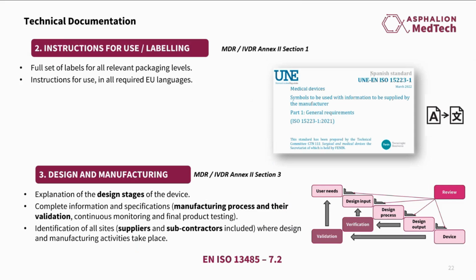Then we have another module, which is regarding the instructions for use and the labeling. Basically, this part of the technical documentation shall include the IFU and the labeling that will be used by the final intended user, so that the notified body can assess how all the information is provided to the intended user and how usability is ensured for this device. Then you also need to have the module of design and manufacturing, which basically defines the design stages for your device, how your manufacturing process is conducted, and the validation processes for the manufacturing of your device.